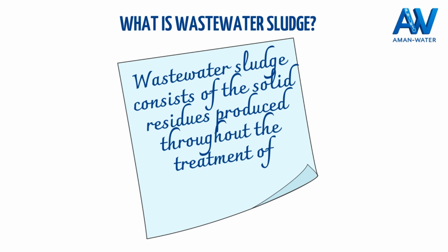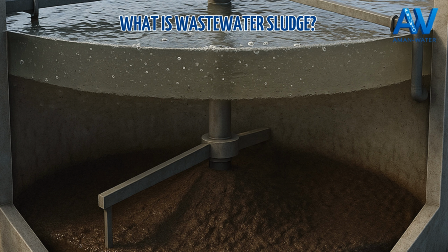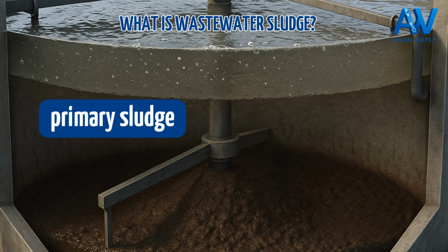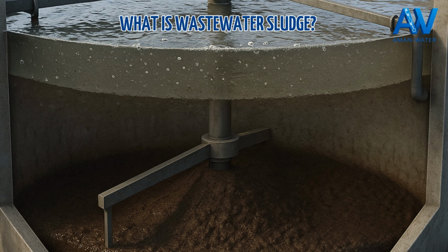From the moment water enters the treatment plant, part of the material it carries begins to separate. This is the origin of the first sludge. During sedimentation, the heaviest particles naturally settle at the bottom. These are called primary sludge. They are made up of suspended solids, sand, settled fats, and organic particles.